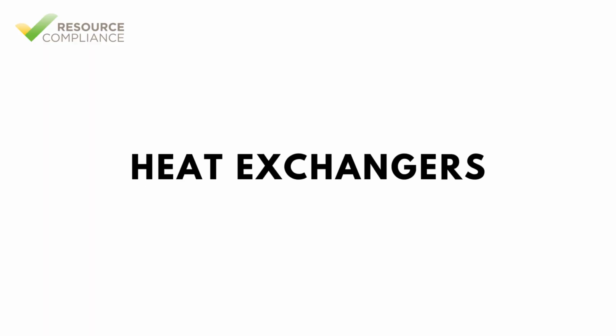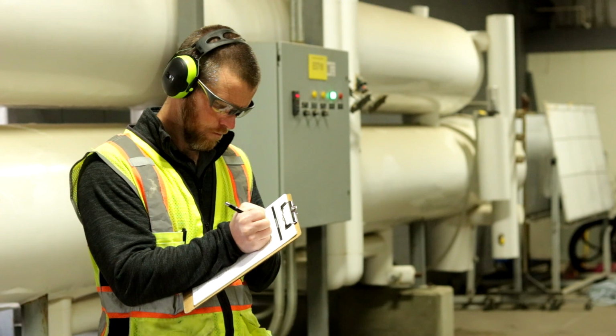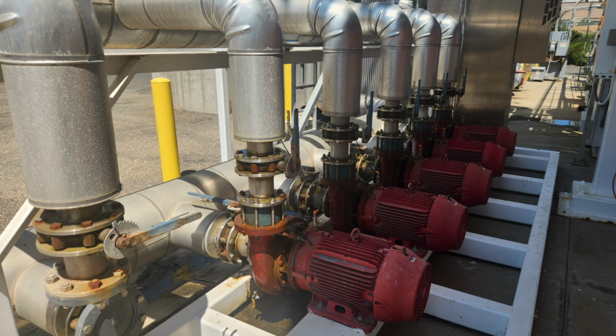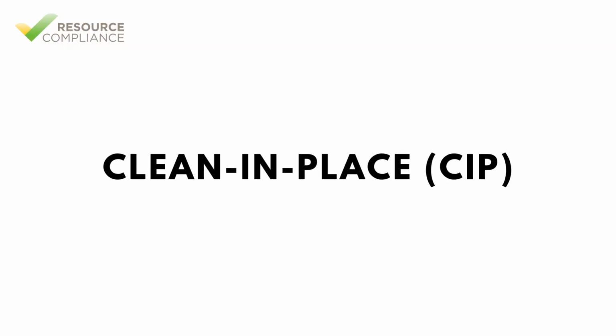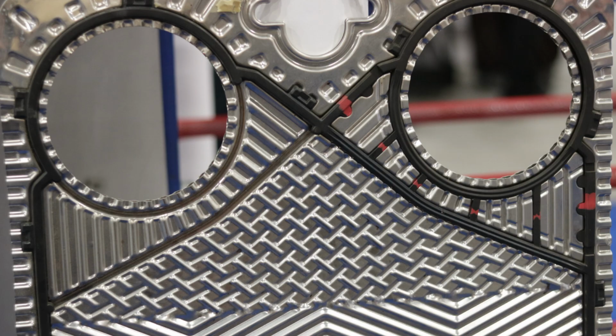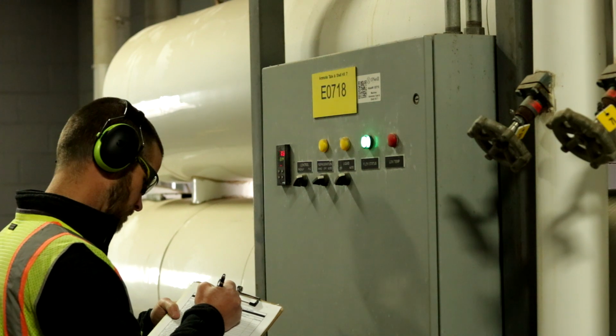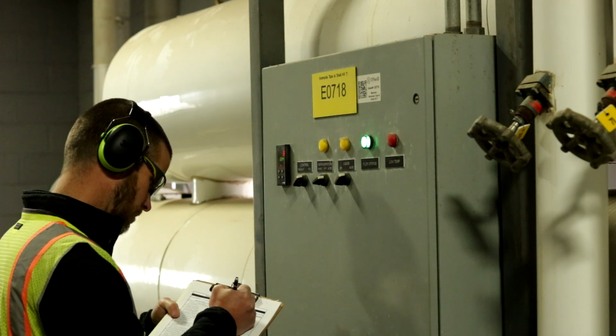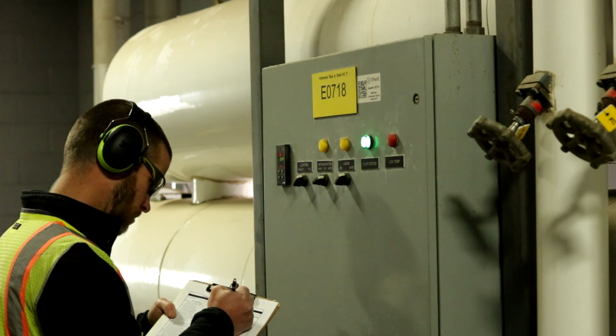Heat exchangers require many of the same ITM activities as pressure vessels. Since these units are often used to cool a secondary coolant, proper secondary coolant flow should be verified annually. If a heat exchanger is used for food processing or beverage application, it will need to undergo clean-in-place, or CIP, in accordance with the Food Safety Program. Plate and frame heat exchangers can be disassembled for a thorough cleaning, although this is rarely necessary. Shell and tube heat exchangers can be mechanically cleaned using tube brushes if scale buildup is severe.